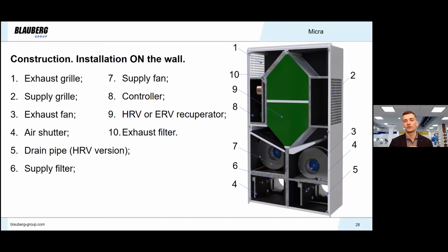Here you can see the construction of the modification that should be installed on the surface of the wall. You can recognize it by the supply and exhaust grills on the right and left sides of the unit. We have applied the following elements in the construction. Supply and exhaust fans with Blauberg AC motors, with impellers with forward curved blades to achieve low noise. Air shutters are built into the unit in order to meet eco-design requirements for decentralized ventilation. The heat exchanger is made from polystyrene, but an enthalpic heat exchanger is available on special request. The drain pan collects condensate from the heat exchanger and evacuates it outdoors through the exhaust duct.